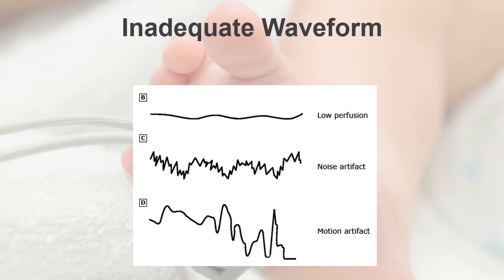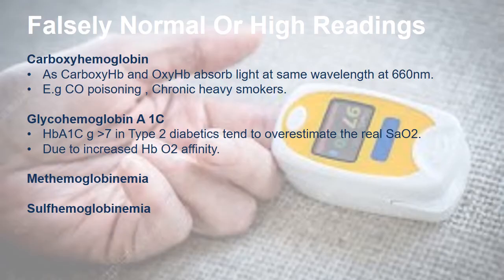Not only inadequate waveforms, you are also not going to get the proper values of SpO2 as well as heart rate. Another thing is noisy artifact. If the patient is moving, that is motion artifact, if the patient abruptly moved, you got a good waveform previously, but the waveform just abruptly disrupts when the patient moves.